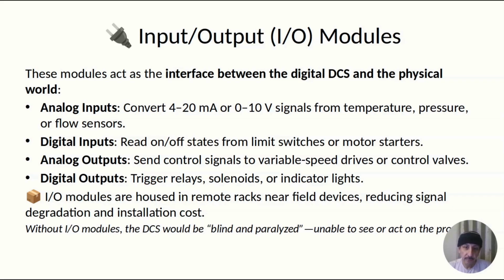Again, notice that if you're using a voltage, you would have to be close to the signal. If you're using a current loop, you might need more energy, but the signal will be the same for the whole current loop. Cost savings. Running hundreds of individual sensor wires back to a control room is expensive and complex. With distributed I/O, only a single high-speed communication cable like a fiber or Ethernet needs to run back to the control room, and this dramatically cuts the installation time and the material costs for the whole system.